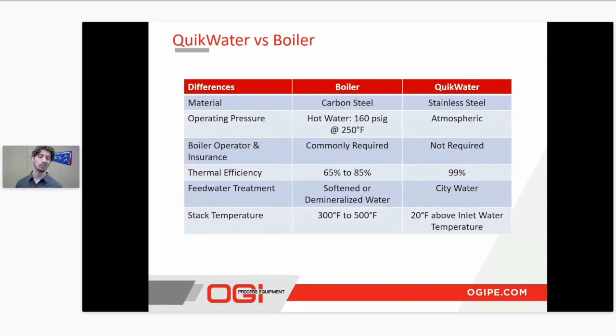As well, boiler operator and insurance, whereas many states have a boiler operator required for their process, as I know we do here in Oklahoma. The QuikWater is not required for that, so your standard maintenance team can work on them and be running at all times. As far as thermal efficiency goes, with a standard boiler being 65 to 85% efficient, the QuikWater in the one-pass situation, with your inlet water at 40 degrees and outlet at 180, is going to be 99% efficient.